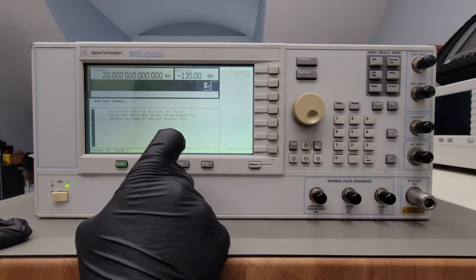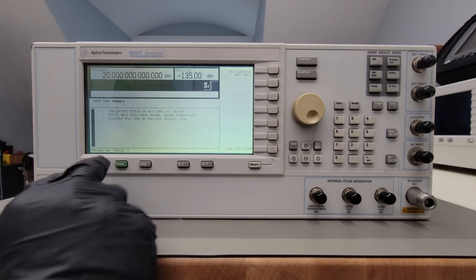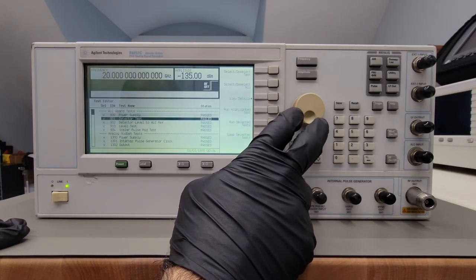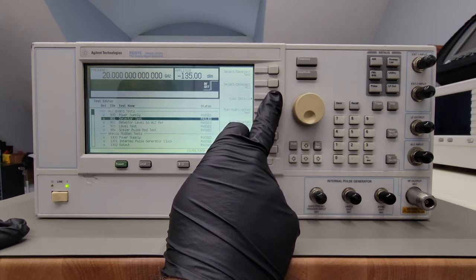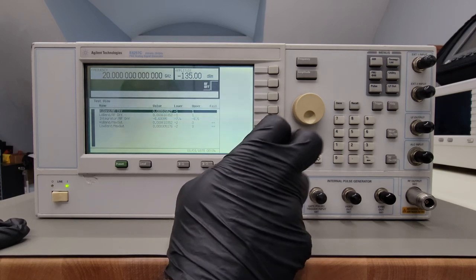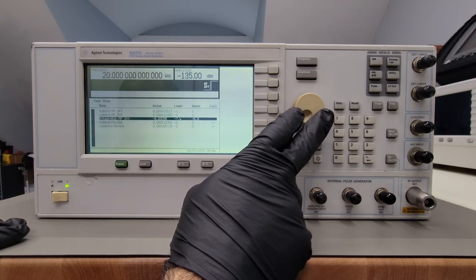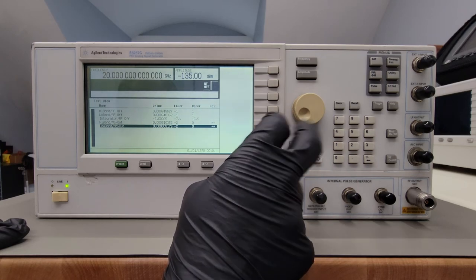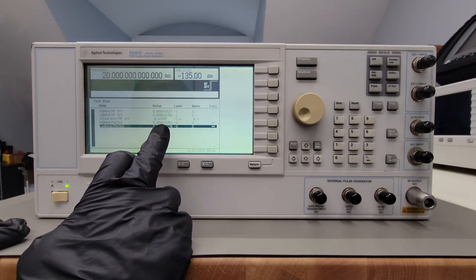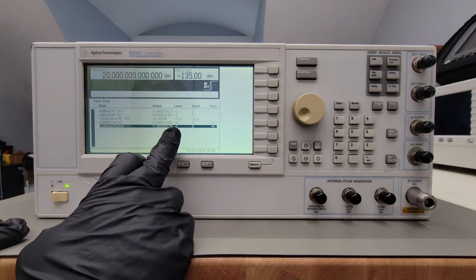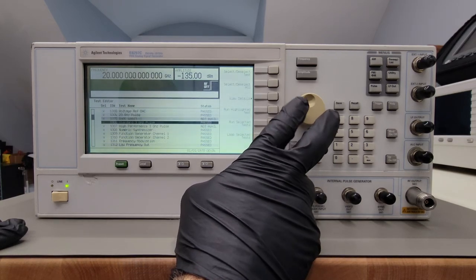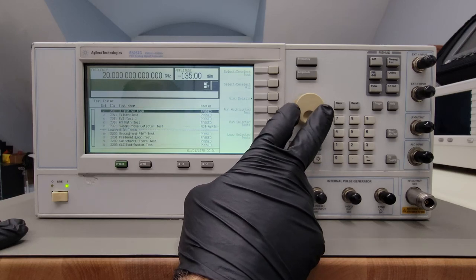We do have the 1204 error, which is the error that this instrument was reported to have. 45 passes, 2 fails. So let's look at the detailed test info. Now I'm seeing over here the first failed test is the 901 error, which is the ALC detector. And if we go over here and look at the detailed error messages, high band max out, low band max out. We'll have to investigate these errors further, but it looks like the reported value was positive and the range for that value is supposed to be between -2 and 0. So we'll have to figure out what this error is. And the other error, I believe, was related to pulse, some sort of pulse mod error.